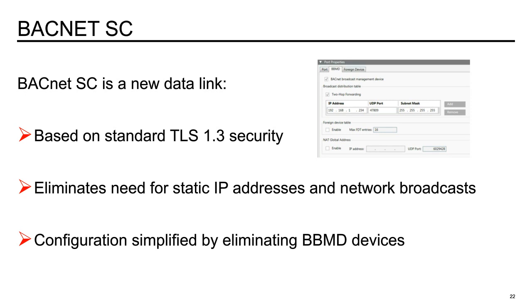The other advantage of BACnet SC is the elimination of BACnet broadcast management devices, or BBMDs, and the need to keep them configured to match network topology. There's no more broadcast distribution tables. So you can see up here on the right, this is a typical table that would be set up in a BBMD. And what happens with the implementation of the BBMD, I have had this happen, if the IT department decides that they want to implement some sort of new IP addressing scheme or network topology, all that stuff has to be changed in the BBMD, and then all the static IP addresses involved with that. It becomes a little bit of a hassle and burden managing that network.